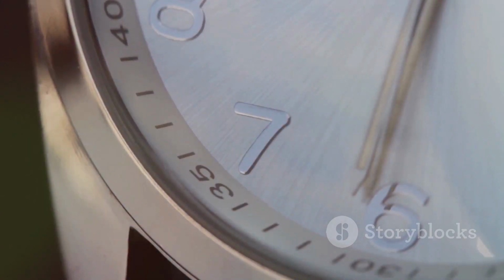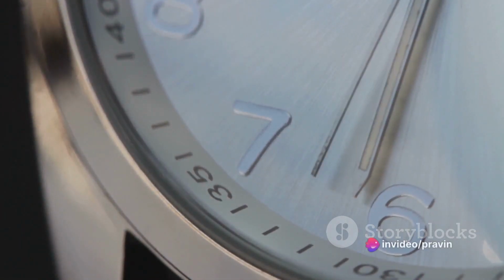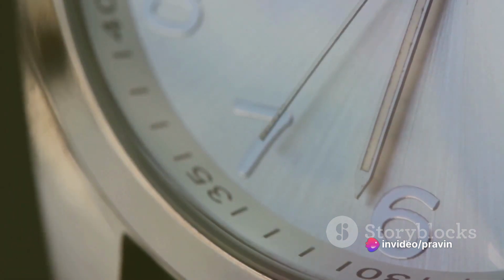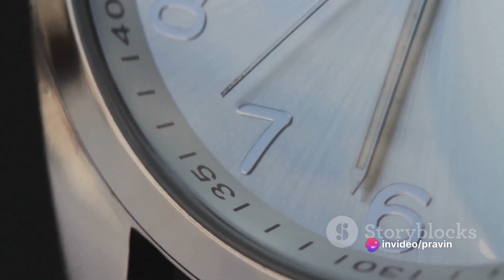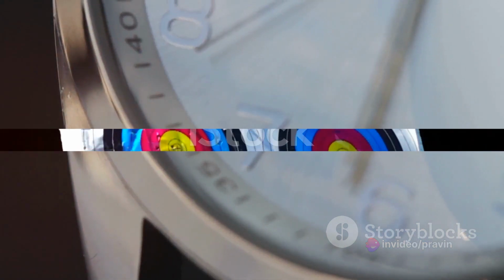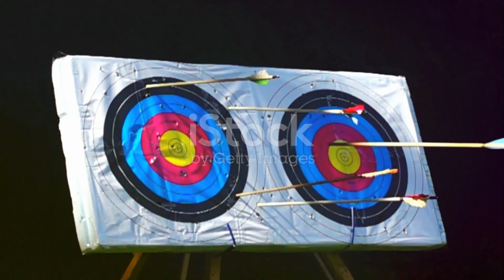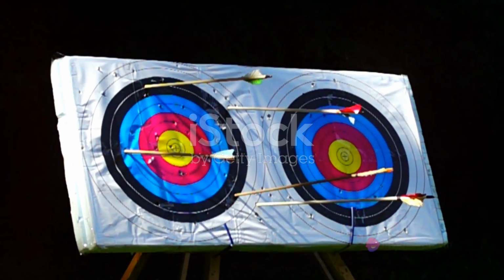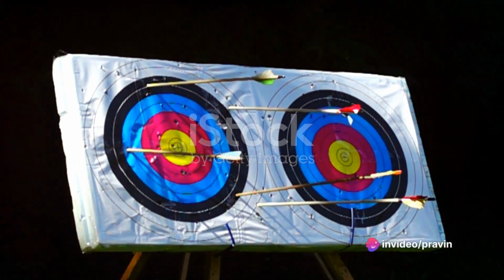Hysteresis is the difference in instrument readings for the same input, depending on whether the input is increasing or decreasing. It could be the difference in arrow positions when moving towards the center versus away from it. Resolution is the smallest change in the measured variable detectable by the instrument. In our game of archery, this would be the smallest noticeable change in the arrow's position on the target.